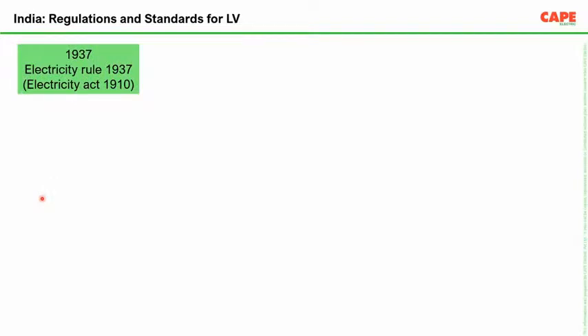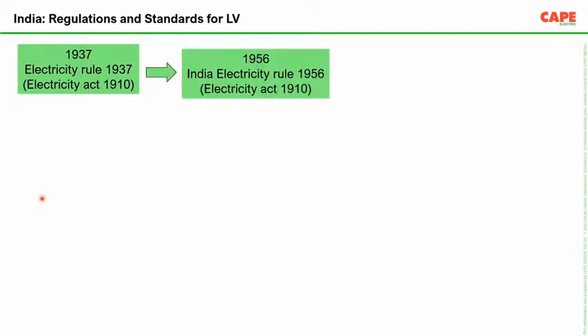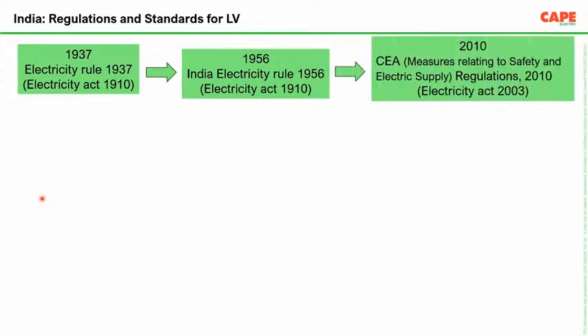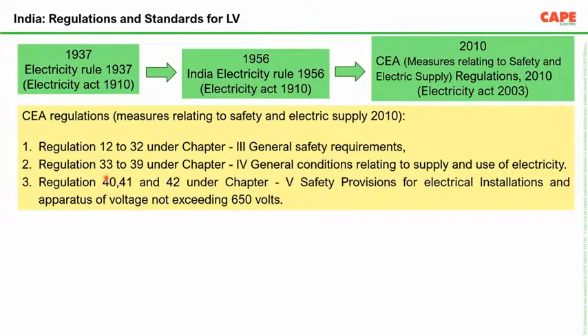Now going back to the regulations of India. In 1937, we had the electricity rule, which was formulated as the Indian Electricity Rule in 1956. And in 2010, the Measures Relating to Safety and Electric Supply Regulation 2010 came, with Regulation 40. Regulation 40 is on testing of an installation, the insulation resistance test. So in the regulation, only the insulation resistance test is shown, whereas in the IEC standard, which I have shown just now, there are 16 different verifications and about 10 different tests.